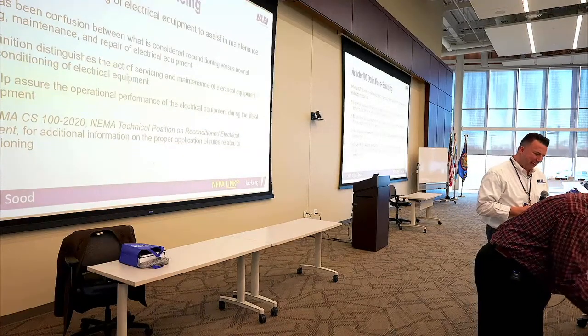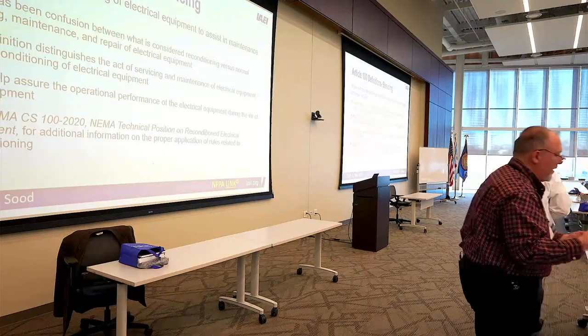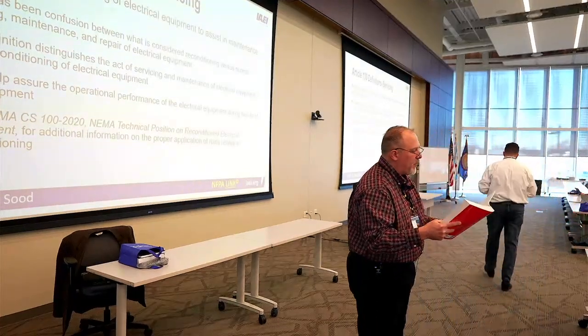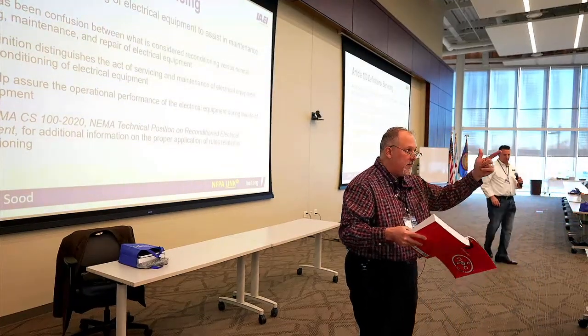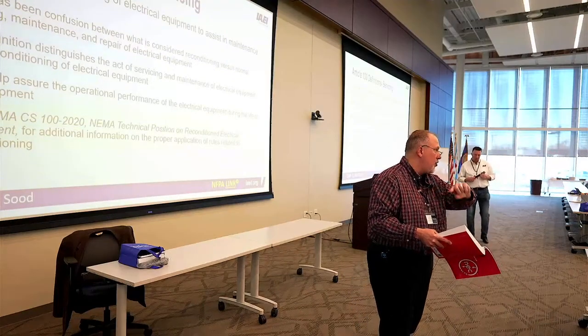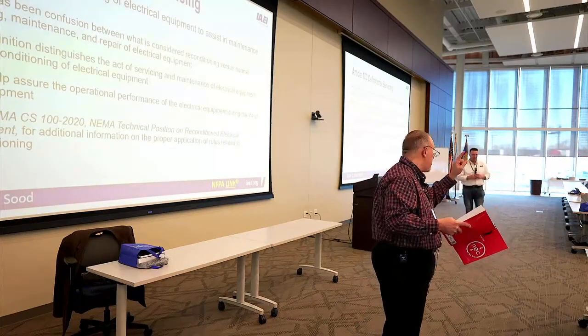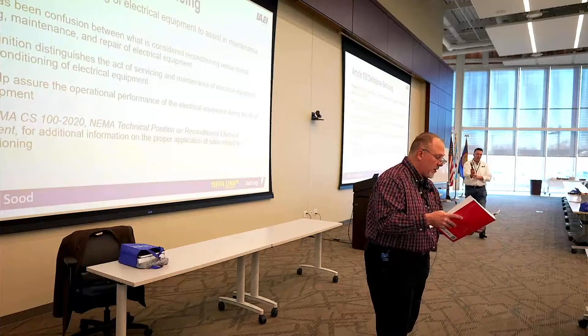Thank you, my walking code book. Reconditioned equipment: it says reconditioned equipment shall be permitted except where prohibited, right? So we said in 240, you're prohibited on molded case circuit breakers, but you're permitted on power circuit breakers.